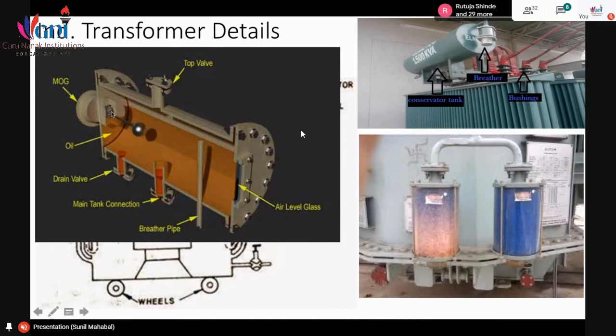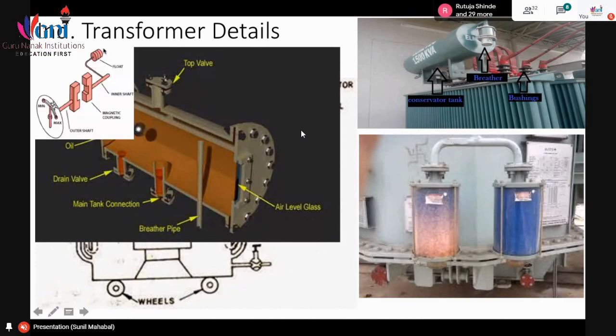It works like this: this part is inside the tank, then there is the flange of the tank in between, and this part is outside the tank. When this magnetic portion rotates with the float, it rotates the outer plate. And this is shown here on the minimum and maximum. So the oil level can be seen from outside. And this is the MOG. It has contacts also, which can be used for tripping the transformer circuit.